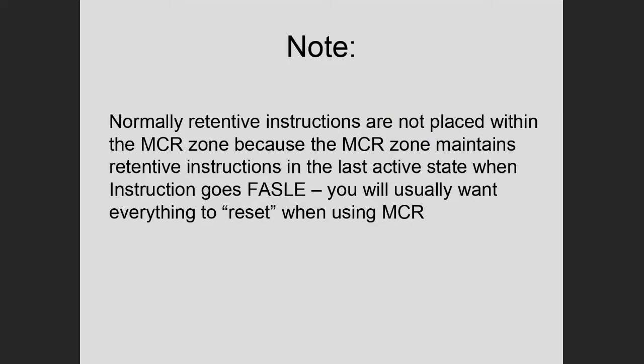Normally, you don't want to place retentive instructions in the MCR zone. Now, it's not to say that you can't do it. If you know what you're doing and you really intend to do that, then it's okay to do it. But most of the time, when you restart a PLC program or some kind of process, you don't want things to come on or to start in the on position. And that's the reason for saying that typically you don't put retentive devices in the MCR zone.